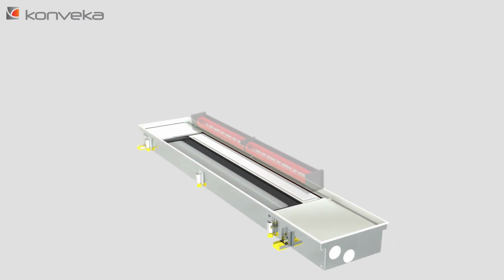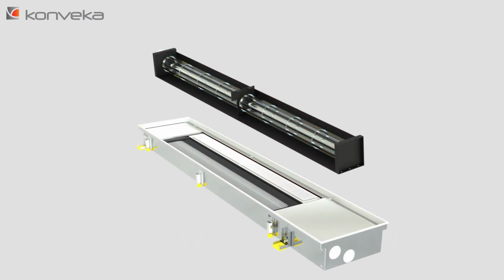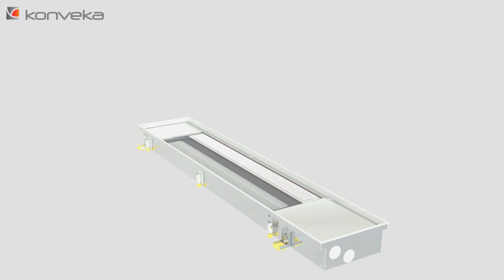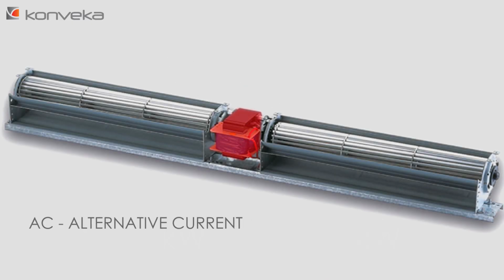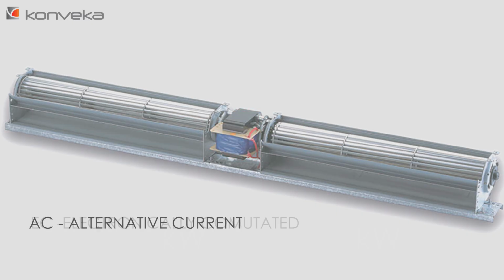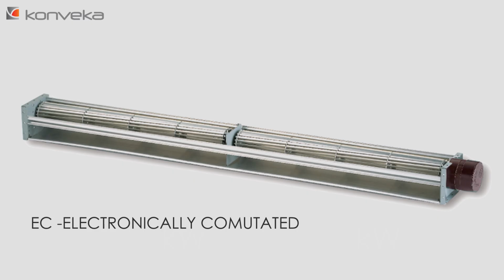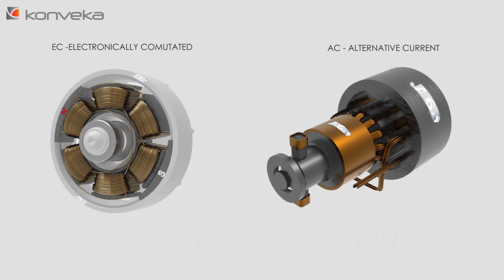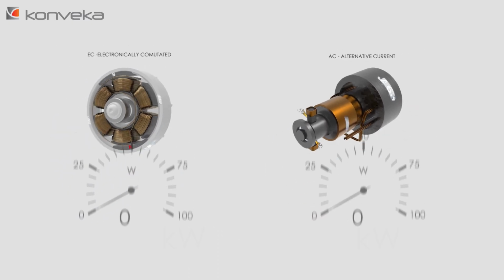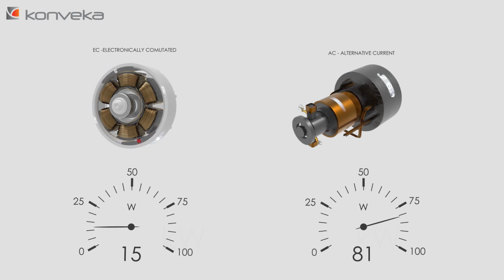Fans. The fan is one of the most important components of a convector with forced convection. The type and quality of the fan determines the service life, output, and noise level of the appliance. Some convectors are still equipped with fans that have outdated technology AC-type motors. All fans in the Konveka convectors are exclusively equipped with EC motors featuring the latest technology. Modern EC technology motors are currently the most efficient and effective motors. Their energy consumption is 84% less when compared to AC-type motors.